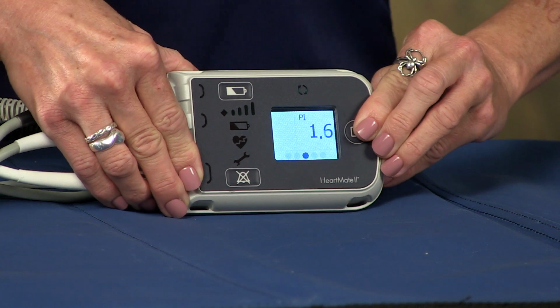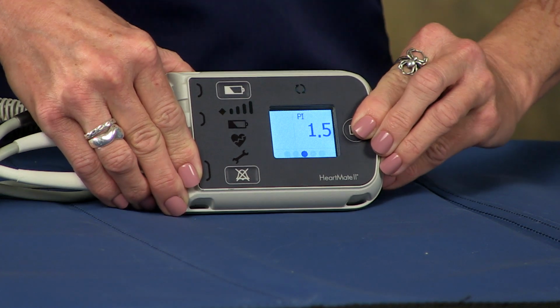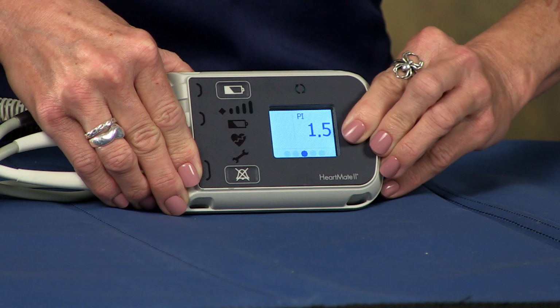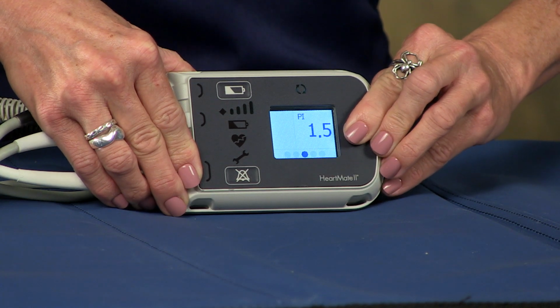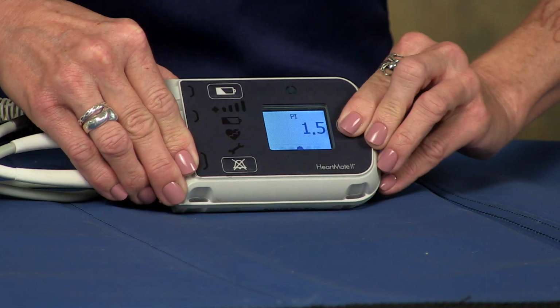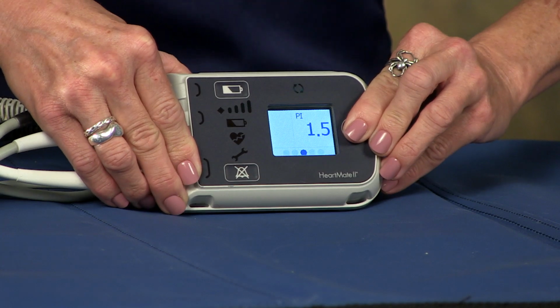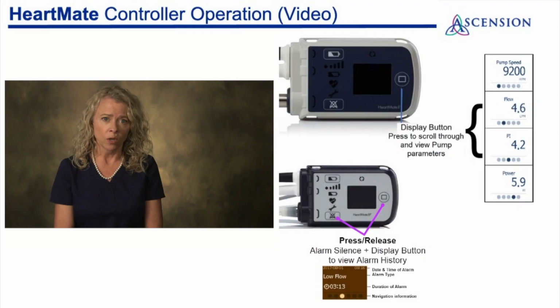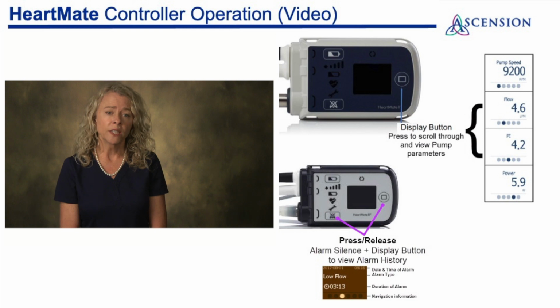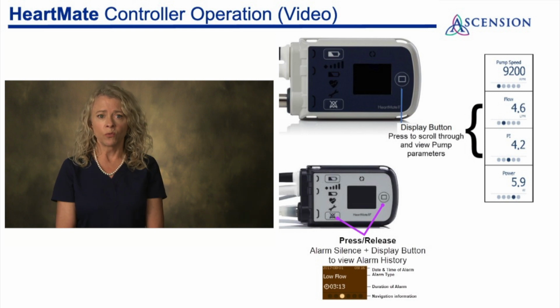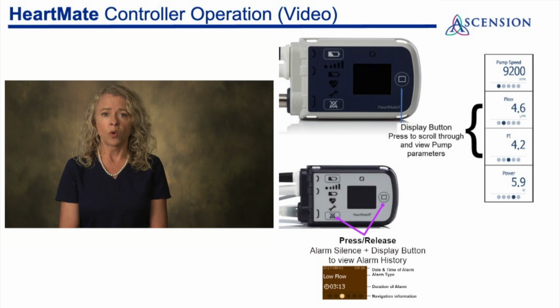This number gives us an idea of how much the pump is assisting the patient. If the pump is doing more work, more blood is being pulled out of the ventricle, and this will cause the patient's pulse pressure to narrow, so the PI will be lower. If the pump does less work, less blood is being pulled from the ventricle, so it will fill and create pressure and exit the aortic valve. This will widen the pulse pressure and is usually associated with a higher PI. We like to see the PI range between 3 and 5.